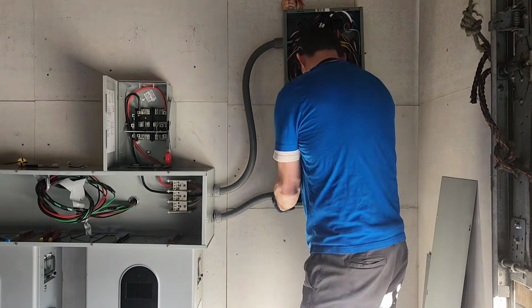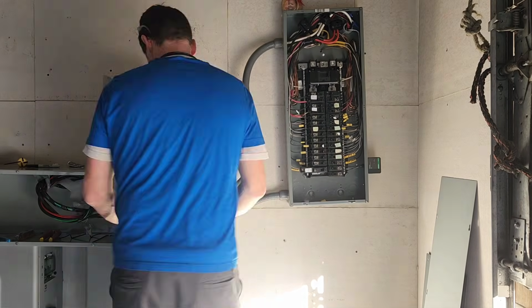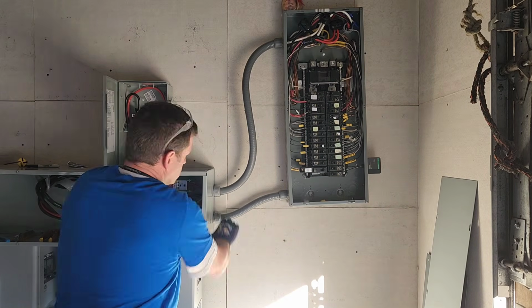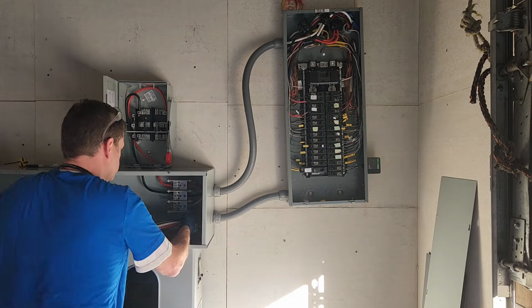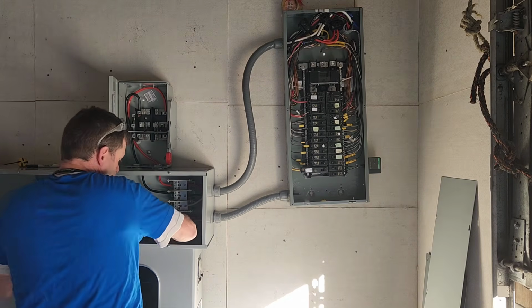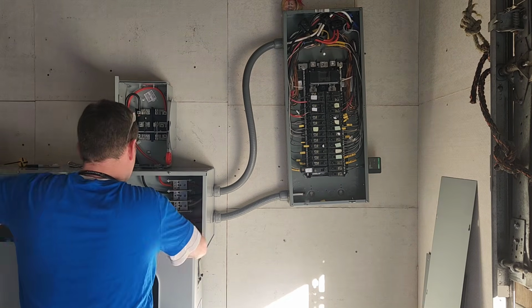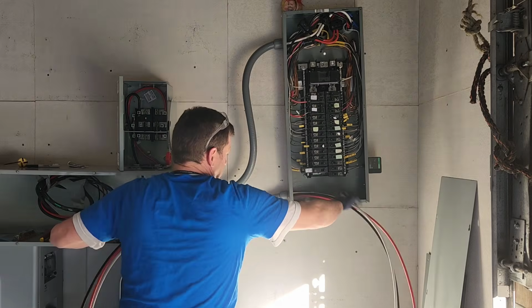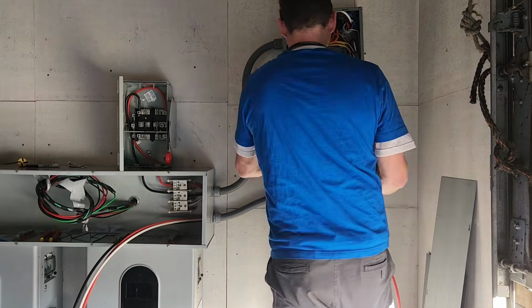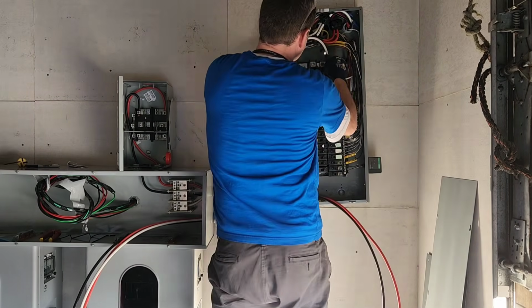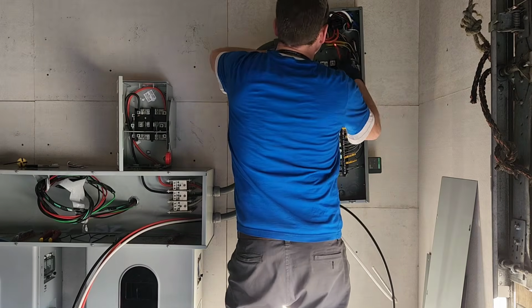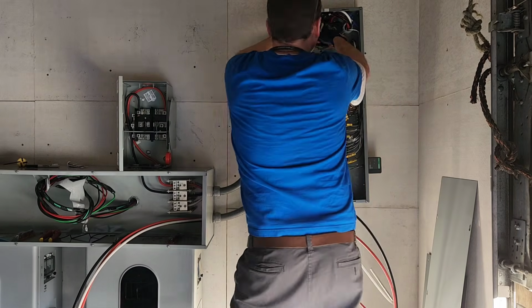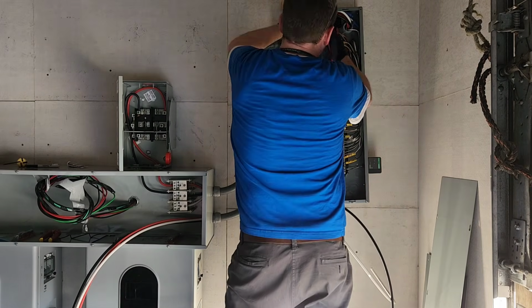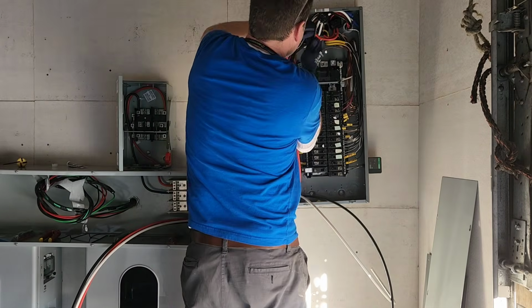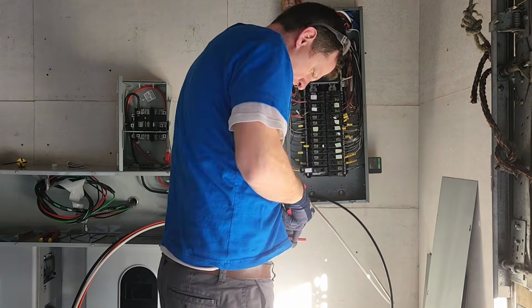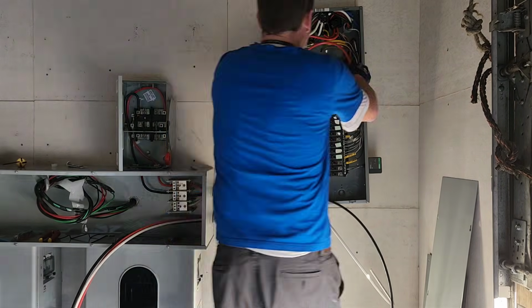Now that I have grid connected into my transfer switch, I need to connect my main electrical panel into the transfer switch. We're going to be feeding these 2-gauge wires through this non-metallic conduit and into the top of my electrical panel, because my main feed from my electrical panel is coming from the top. These are going to land right in the top lugs of my electrical panel.